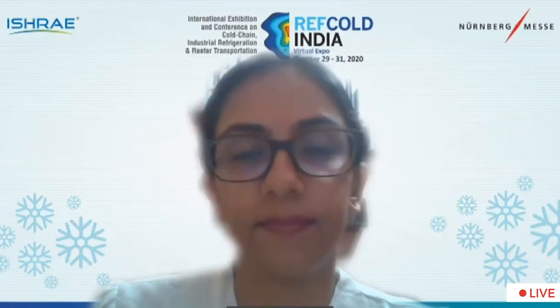Thank you for that answer. Our next question would be, which refrigerant is the best for CO2 cascade systems? So, ultimately, it's going to be a trade-off between efficiency on the cascade system. So there are different refrigerants available. And I can provide another reference to a paper that talks more about different refrigerants in the cascade system. It might be useful, and I'll add that to this presentation. But the trade-off also will be trying to get the lowest GWP refrigerant on the cascade system.